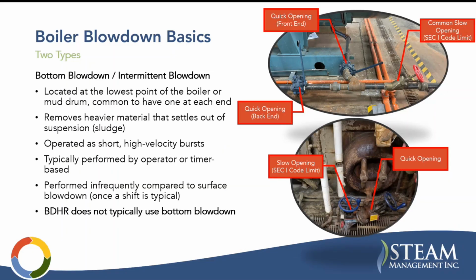The other main type of blowdown is bottom blowdown or intermittent blowdown. I should say that's not what this presentation is about, but I'll go through it real quick. This is located at the lowest point of the boiler or mud drum in a water tube boiler. It's common to have one at each end, and basically you have two valves on each end, or maybe a common one. This is your slow opening valve. The procedure is you open this slow opening valve, and then this is your quick opening valve. You see the big handle there. You can quickly open that, and you're going to blast water out of the bottom of that boiler to try to remove sludge. So not dissolved solids, but settled solids for the most part.